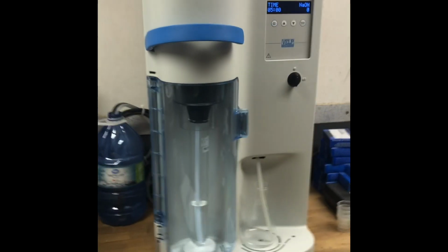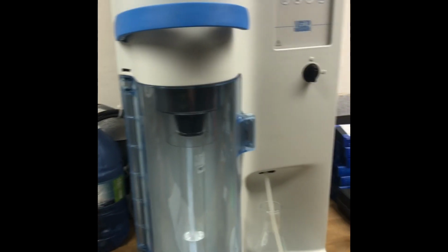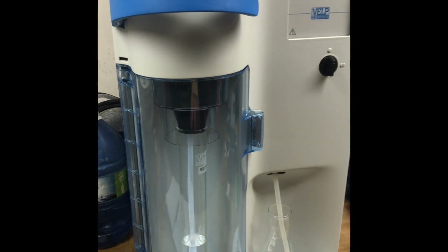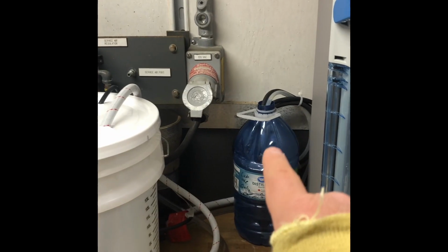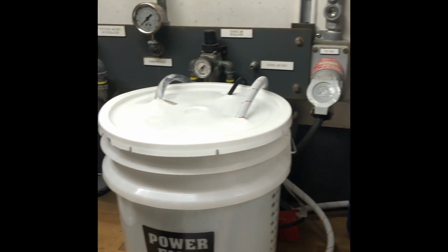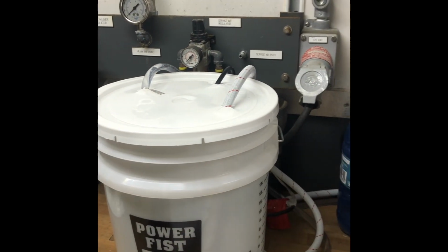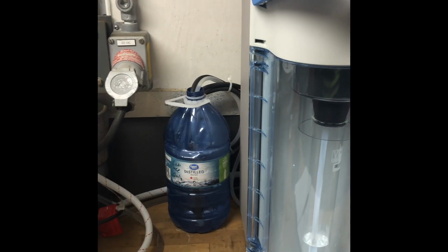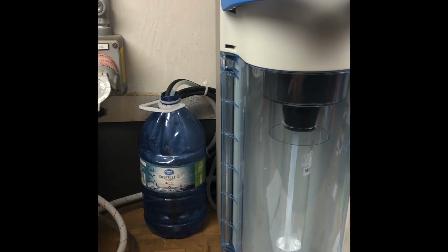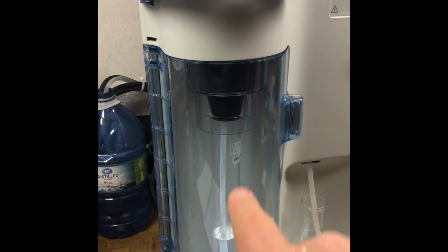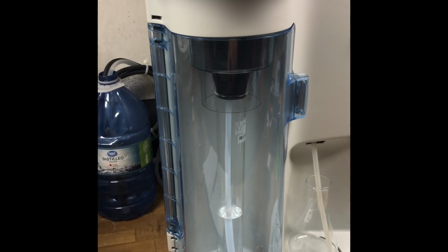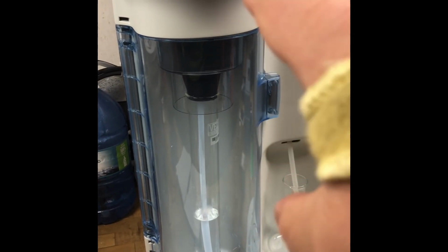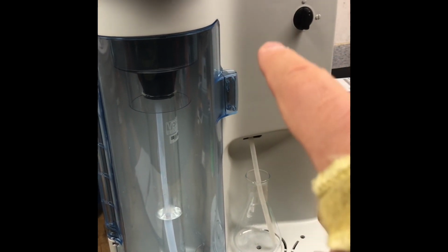So the way this works is I put my sample in this large test tube here, and I've got a distilled water reservoir and a cooling reservoir with tap water. So it's all automated. What'll happen is the machine will take in distilled water, it'll generate steam from it, and it'll inject the steam down into the sample.